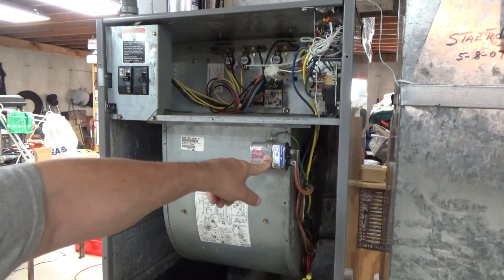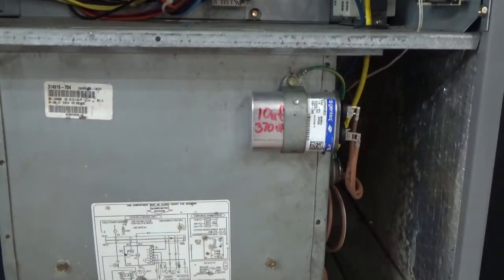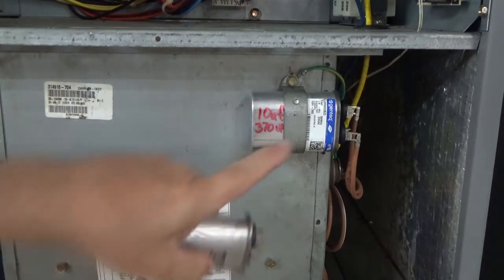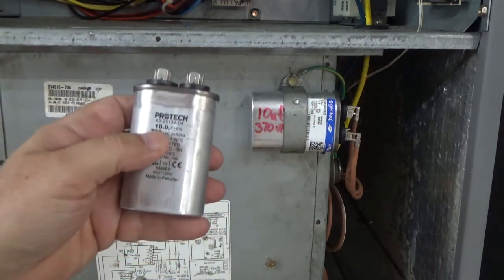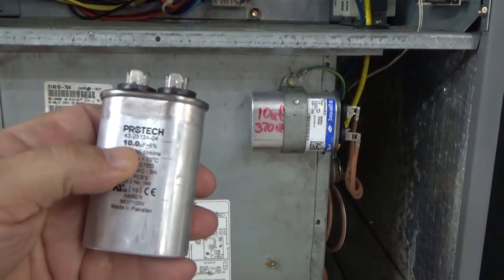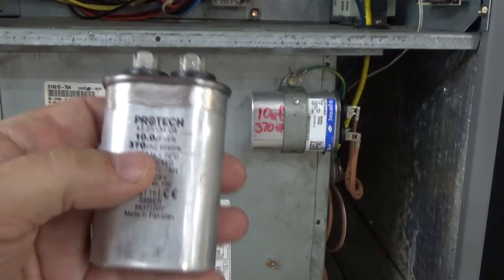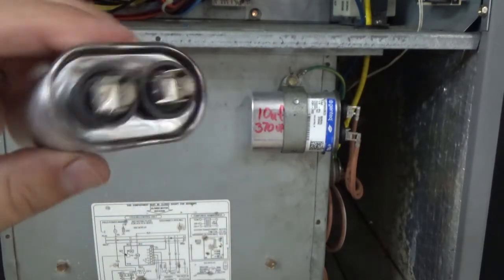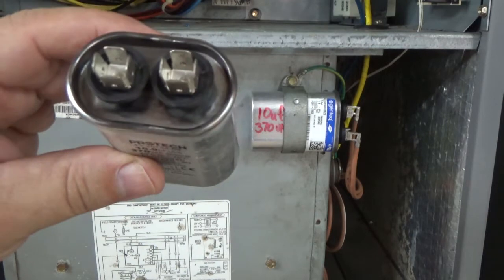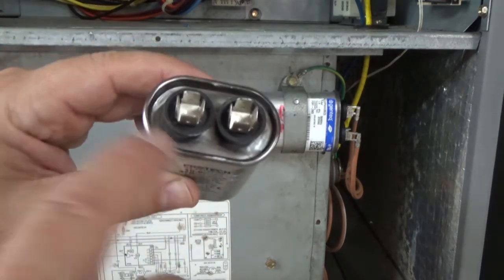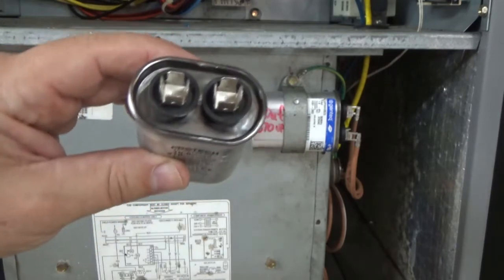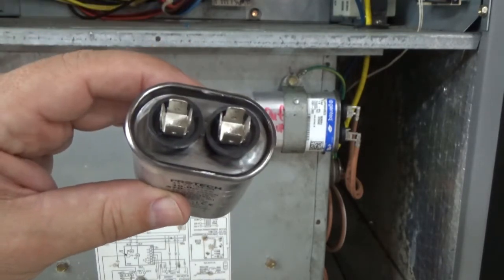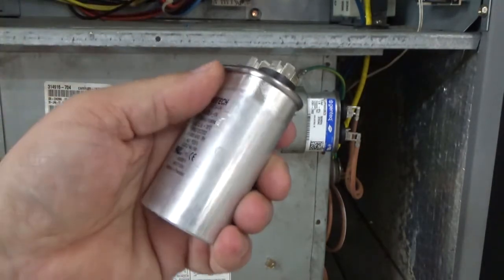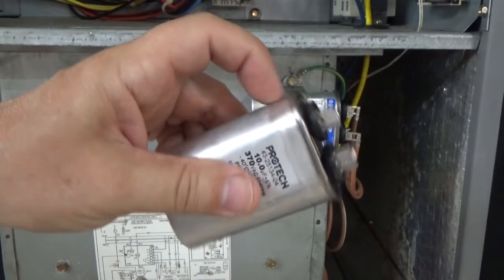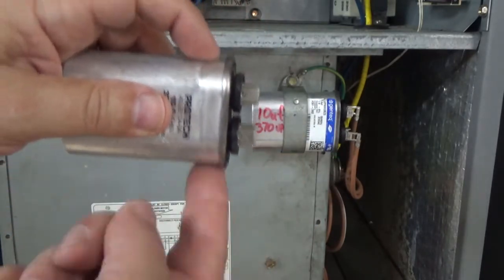This guy could be charged. Oh, let me show you something. Alright, if you do find this bubbling out and you need to replace it, maybe the fan's not working, you can read the tag, and the important numbers are the microfarads, this one's 10, and the voltage, 370 volts AC. And it has 2 connections on it. And what you want to notice is that this is flat. If you see it bulged out, if it's still working, you're lucky. And if not, you know what's wrong. Also, if you see oil on them, that's bad too. If you see oil dripping off the end here, bad news.